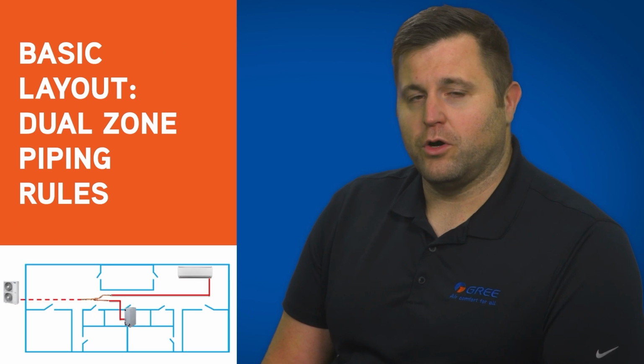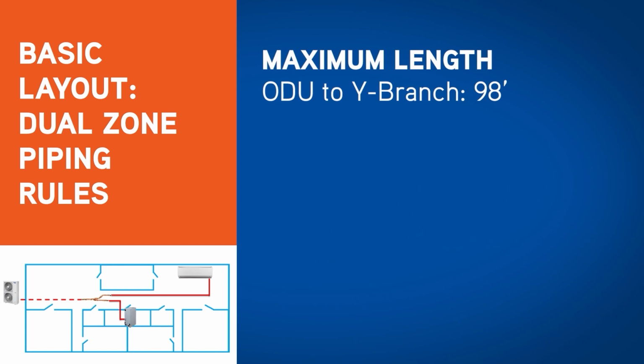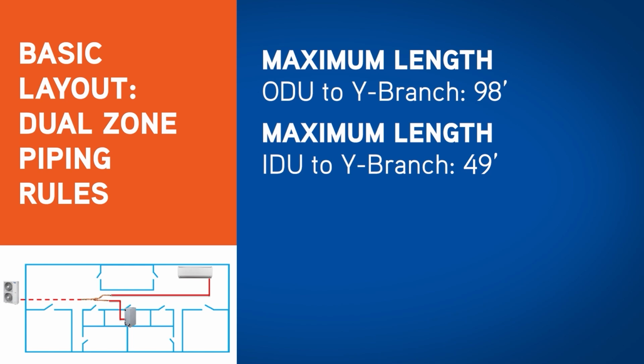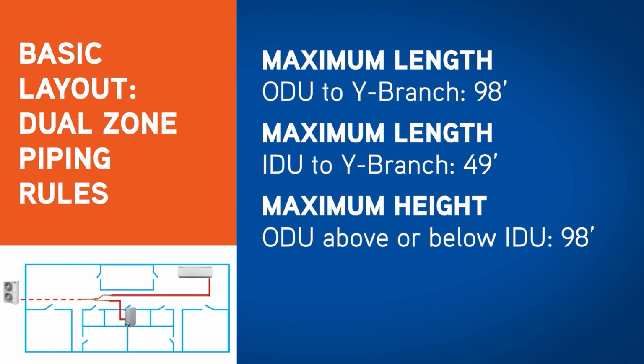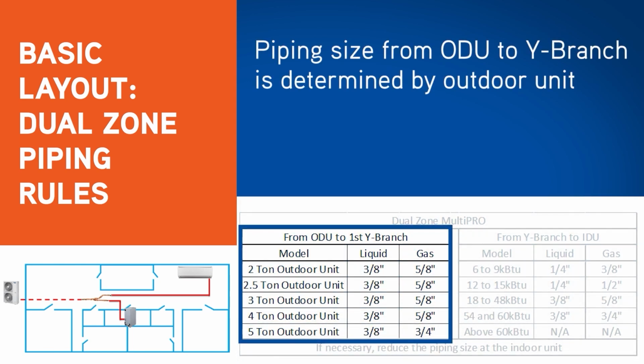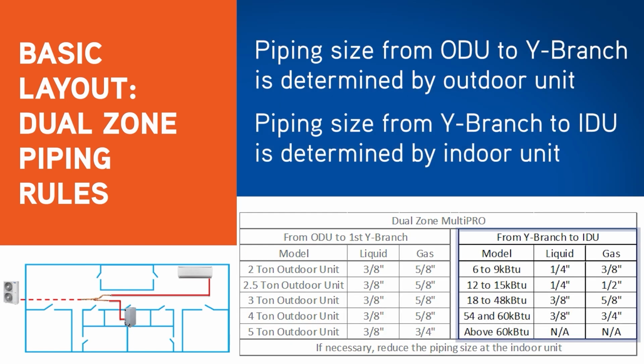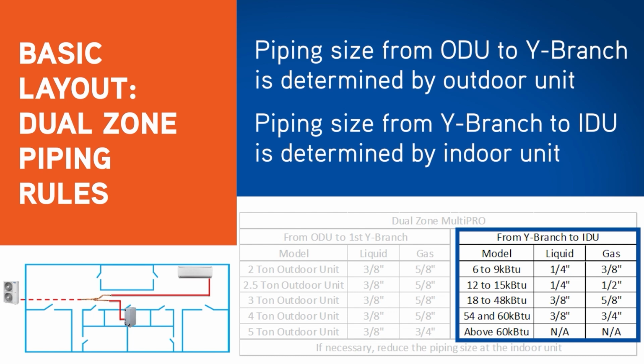A little more complex than the single zone basic layout, the dual zone basic layout has shorter overall line set limitations to keep things simple. The maximum length from the outdoor unit to the Y branch is 98 feet. The maximum length from the Y branch to either indoor unit is 49 feet. The maximum height difference is 98 feet, just like the maximum line set length. The size of the main piping, or the piping from the outdoor unit to the Y branch, is determined by the capacity of the outdoor unit. The piping size from the Y branch to the indoor unit is determined by the capacity of the indoor unit. In most cases, smaller rooms will be using 1/4 and 1/2 inch, while almost all larger spaces will be using 3/8 and 5/8 line set.